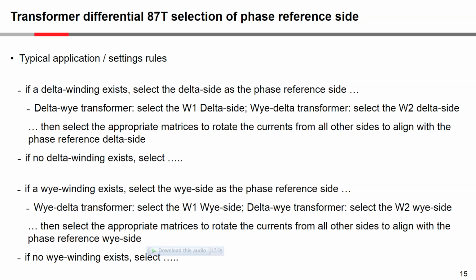Or you could be faced with a different set of rules. If a Y winding exists, select the Y side as the phase reference. So in other words, if we have a Y delta transformer, then we need to select the Y side, which is the winding 1 side. If it's a delta Y transformer, then we need to select the winding 2 side. Okay, and then the appropriate matrix for the other equations. So yeah, we have two different approaches. One set of rules is telling you to go one way, and another set of rules is telling you to go another way. Why should that be?